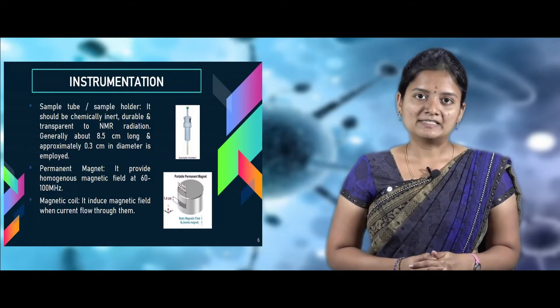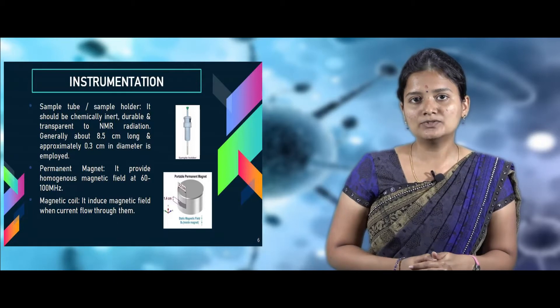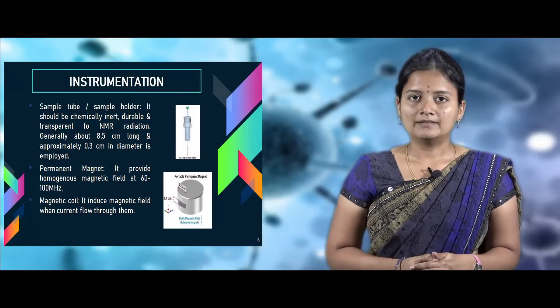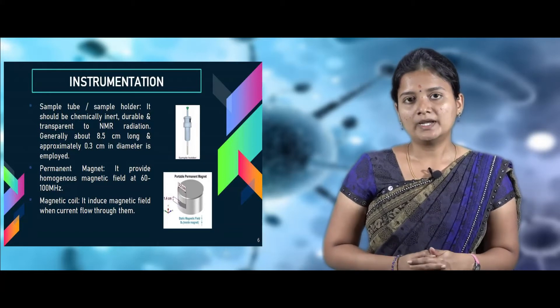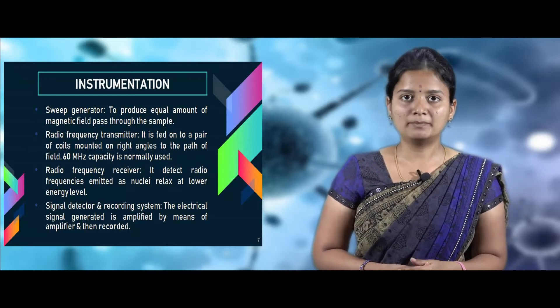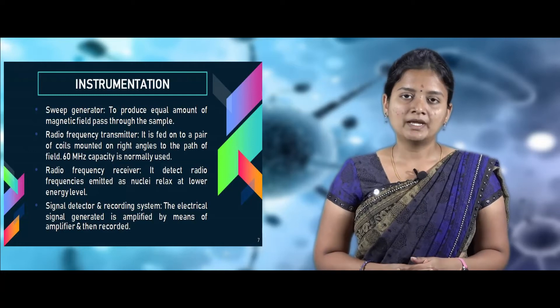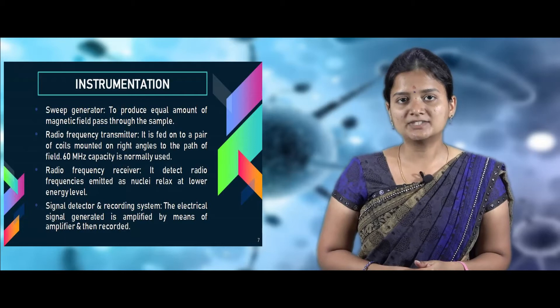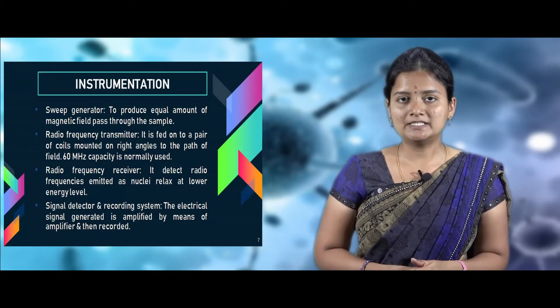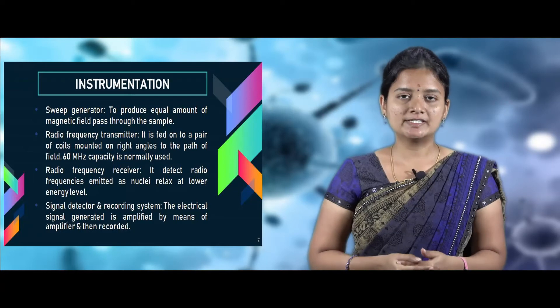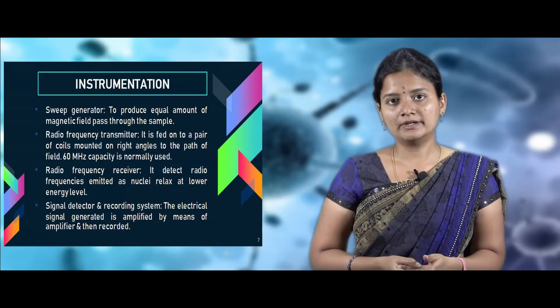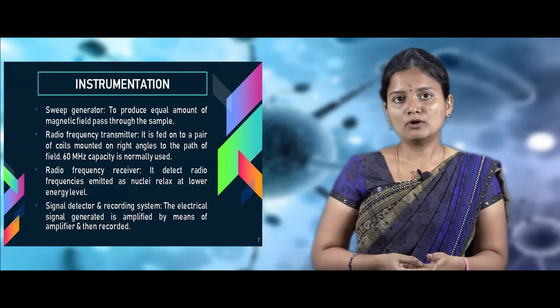The permanent magnet helps to produce a magnetic field at the frequency range of 60 to 100 MHz. The magnetic coil induces a magnetic field when current is passed through it. The sweep generator produces an equal amount of magnetic field across the sample surface. The radio frequency transmitter transmits radio frequency to a pair of coils at approximately 60 MHz. The radio frequency receiver receives frequencies emitted by nuclei at the lower energy level. The signal recorder, the final component, amplifies all recorded signals.